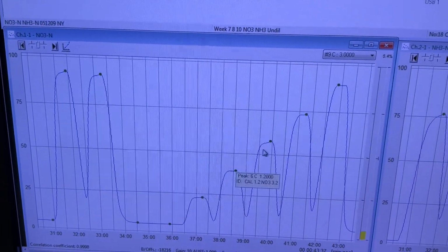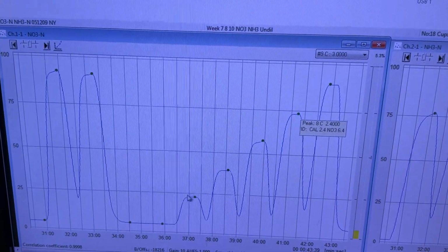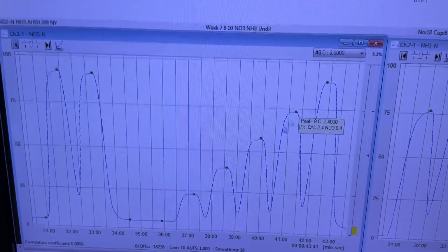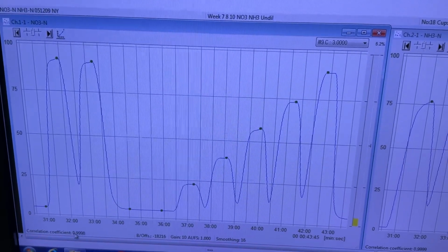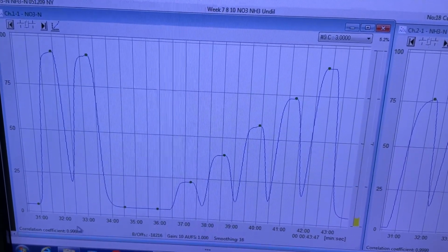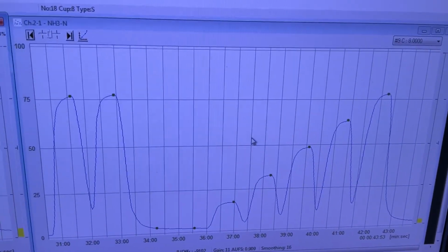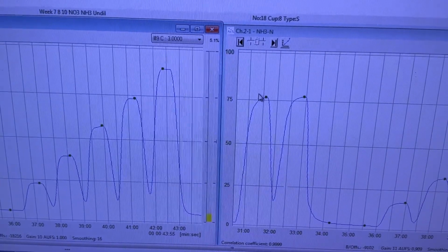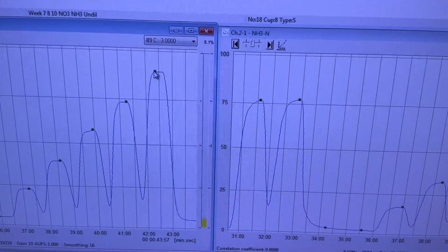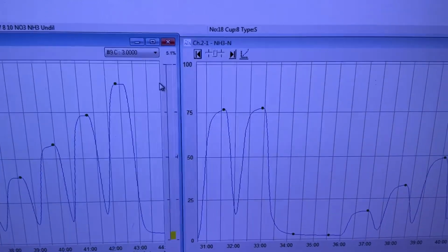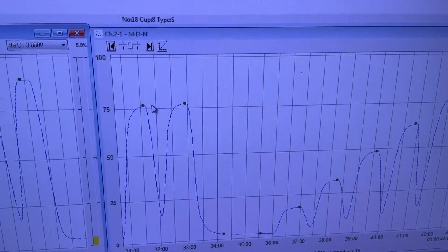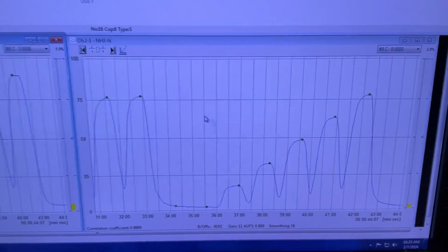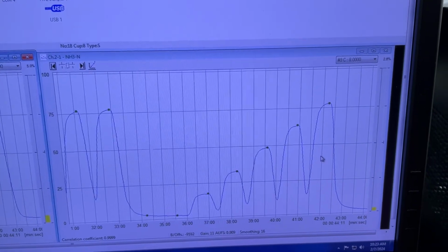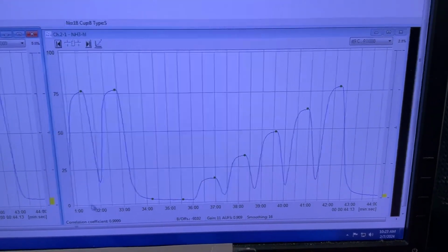And you want to look for like a 1.0 correlation, but what you end up really with is like a 0.99 something usually, which is very, very accurate. And this is all based on how strong your expected nutrients are going to be in your solution. So if you can expect that maybe your nutrient profiles are going to be higher in concentration than your highest known standard, then you're going to need to dilute your solutions to actually get them within the detectable range of this machine. So those two curves that I'm pointing my cursor at right there and that last one, that's the highest known standard for that analysis for ammonium right there. That's actually around 8 ppm, just to let you know.